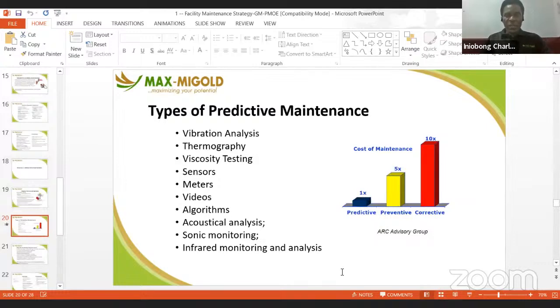So, types of predictive maintenance. This kind of maintenance can be achieved by using devices and other equipment to monitor the condition of your assets. For example, vibration analysis, thermography, viscosity testing, like testing the oil in your generator.